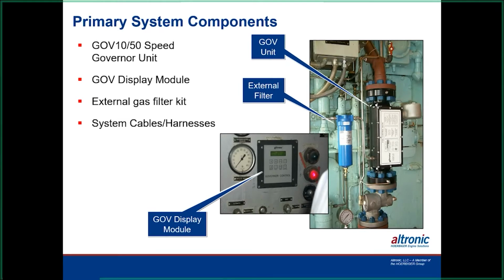So it does not affect the performance of the valve any. It's just when it comes to measuring the fuel going out. If you're looking for an accurate fuel measurement on it, you need some straight pipe going in and out of the valve, so you get clean flow without any turbulence in it. So keep that in mind if you plan on using that portion of the valve.